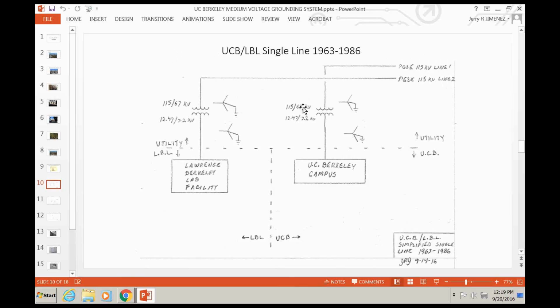Line 1 came in and fed our transformer, 115 kV primary, 12.47 kV secondary, fed our campus. The transformer was owned by the utility at that time. The primary winding was solidly grounded. Secondary winding was solidly grounded. And likewise, over at Lawrence Berkeley Lab, they had a very similar setup, same voltage ratings, same situation in that the utility was in charge and operated all this equipment here. On the other side of the dividing line was the UC Berkeley campus, and then in its own little section was Lawrence Berkeley Lab. So it operated that way for a long time. I can't say too much about how well it worked because I wasn't here. Haven't heard about any real problems, though.